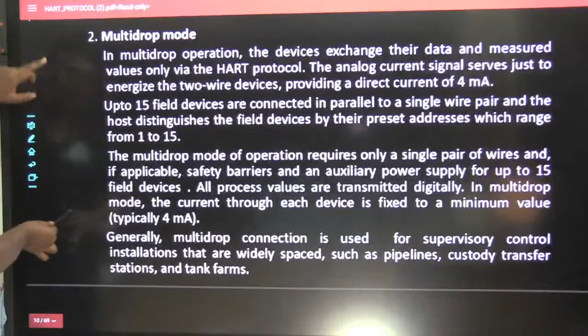Okay. So, just go through this content that I have collected; it is available on the net, you can search for HART and get a lot of content. In multi-drop operation, the devices exchange their data and measured values only via the HART protocol. That is the point you have to understand. The analog current signal serves just to energize the two-wire devices, providing a direct current, just to enable the line current loop. Remember, my dear, how many devices can be connected? Up to 15 field devices are connected in parallel to a single wire pair, and the host distinguishes the field devices by the preset address.